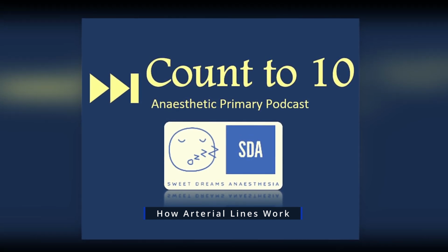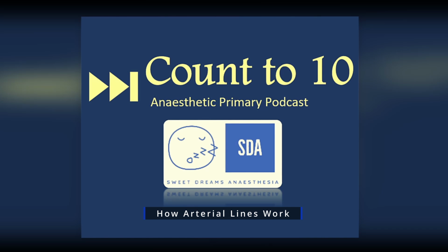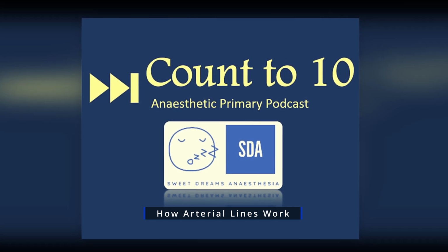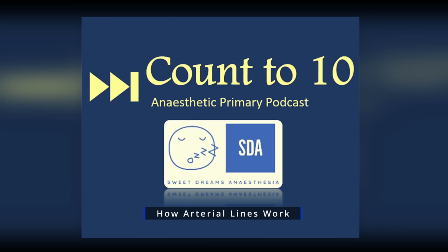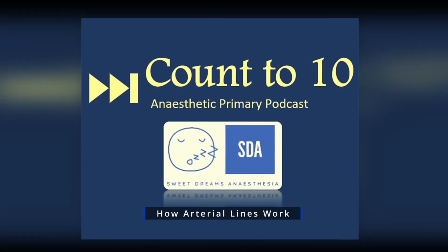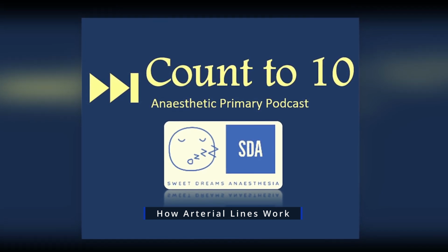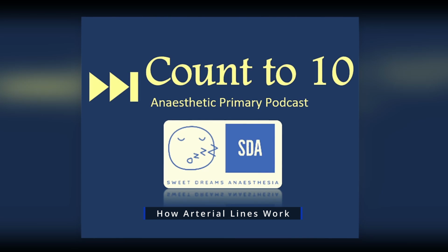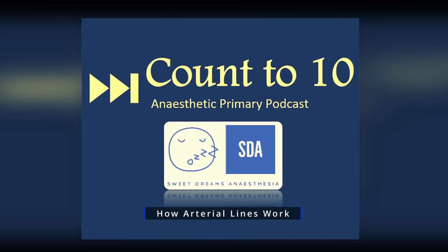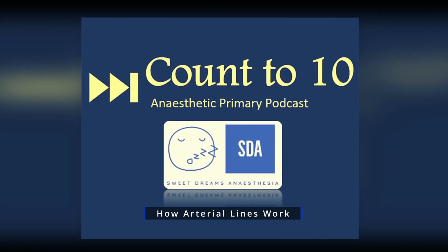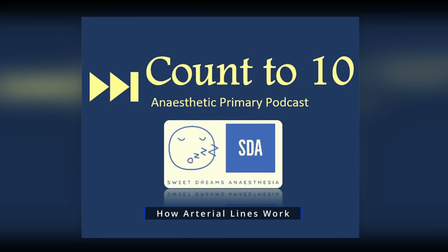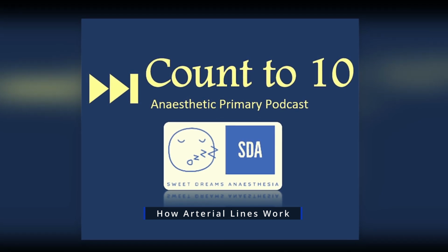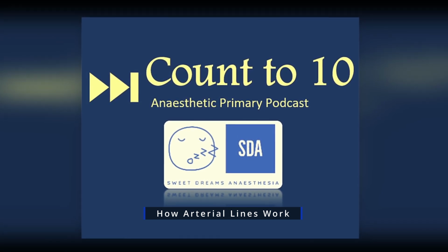Hydraulic coupling is essentially just the preservation of energy. So it's the preservation of that pressure energy carried to the transducer, which is the next step, where it can then be converted into an electrical energy. If during that length, that pressure energy diminished, the electrical energy picked up at the transducer would not be an accurate reflection of the patient's blood pressure.